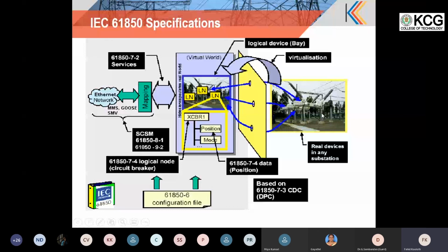Now we want to represent this in the standard. So the first thing is to virtualize the real things into a virtual world, copying all the real entities and their functions. What they did is segregate it into multiple functionalities in a substation. Breaker operation is one functionality. Overvoltage protection is one functionality. Undercurrent protection is one functionality. Disturbance record collection is one functionality. Metering is one functionality. Measurement is one functionality. Like that, they classified all the functionalities in a substation, and these are represented as logical nodes.